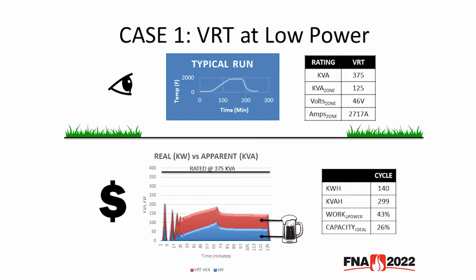Also note the line above, which is the maximum rated electrical capacity of the furnace at 375 kVA. This is remarkable because the real power required for this run never exceeded 120 kW. In other words, the maximum power of this cycle was only 26% of the ideal rated electrical capacity of the furnace. This is not good for power quality.